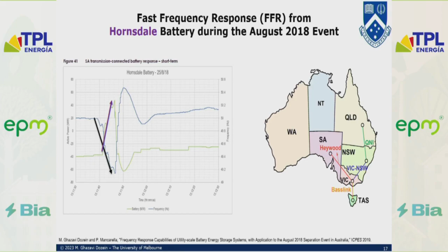But let's see how battery provided frequency control during the August event that I explained. At the time of the event, the battery was charging and then the frequency dropped, so basically you had load more than generation. The battery started to reduce its active power consumption and inject power to mitigate the active power mismatch in the system. But then South Australia separated.